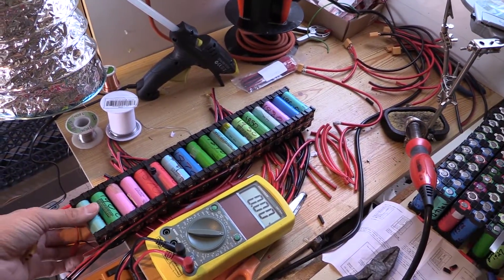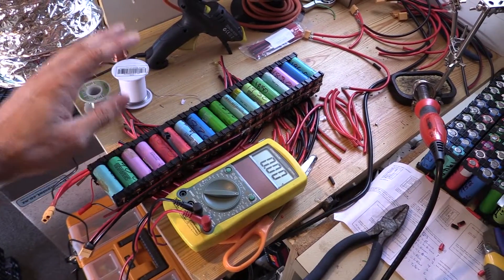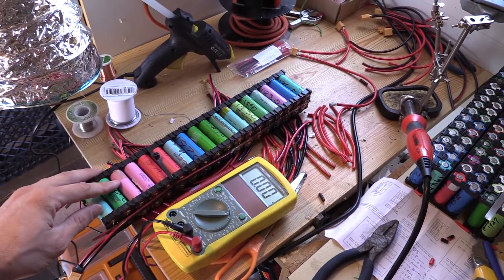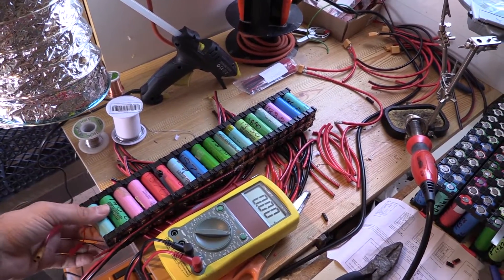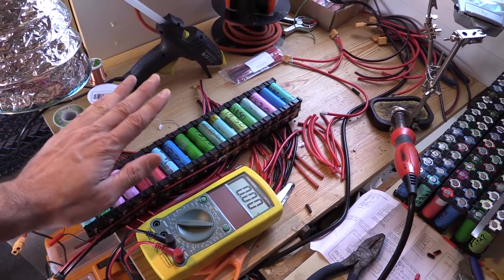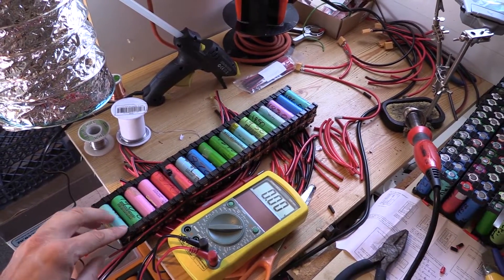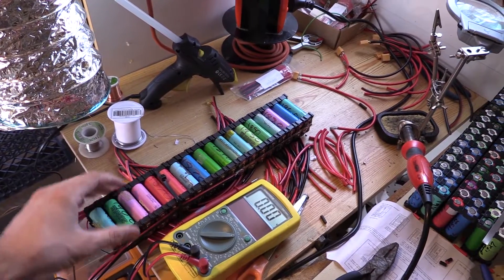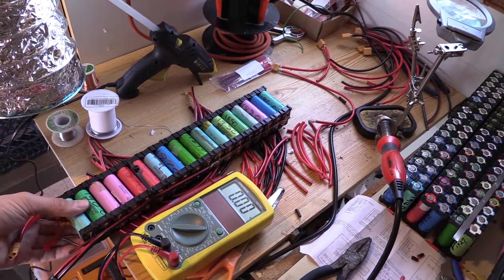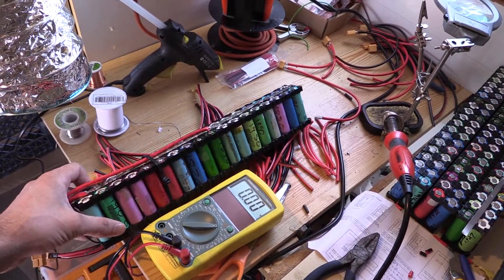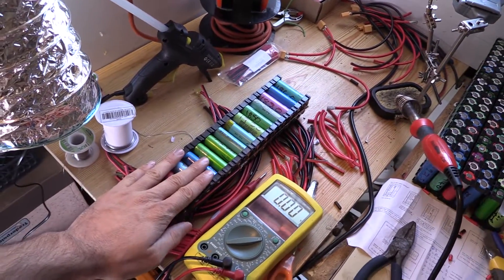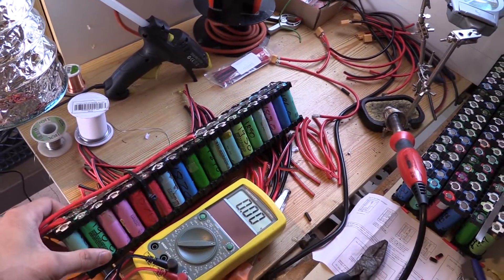In the short term I've thrown another pack in. The problem is that pack is out of balance with all the other packs in the power wall, which creates issues. As soon as a fault like this occurs, the best thing is to turn the power wall off and start figuring it out before voltages drop to zero. It would've been nice to catch this at maybe three volts.